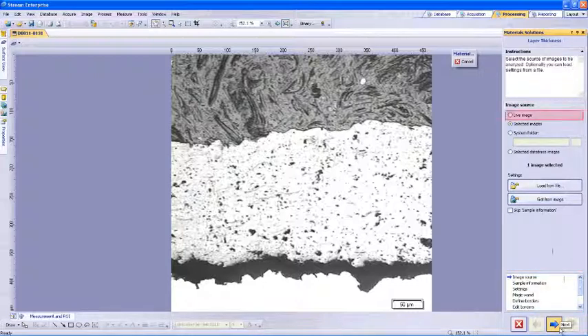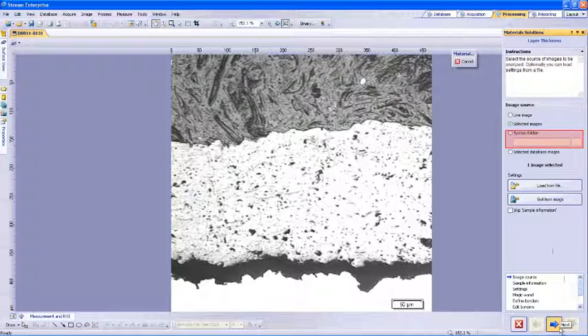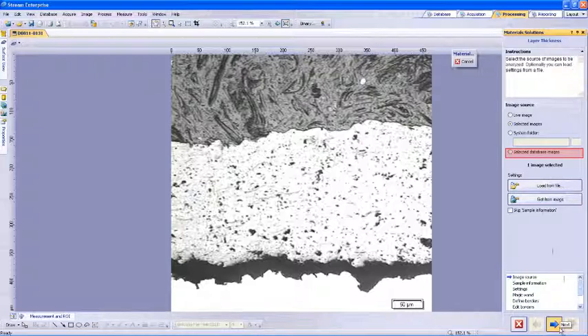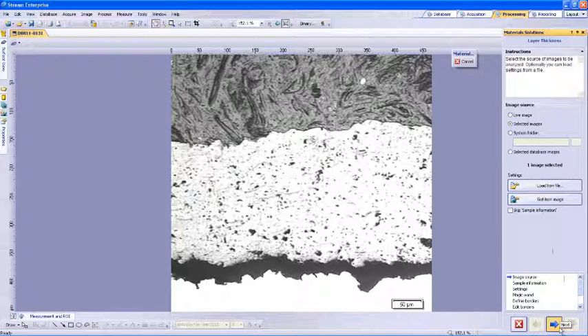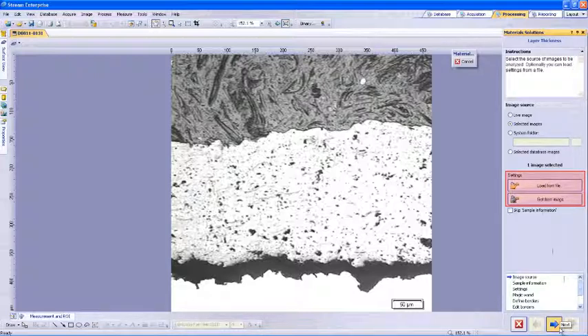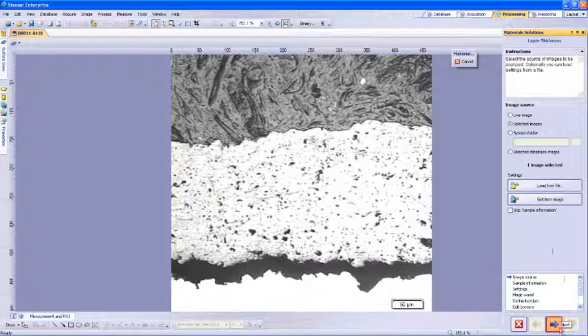The image source selection can be from a new live image, the selected image already opened within the software, a batch of images located within a system folder, or a batch of images you select within the optional Olympus Stream database. The ability to process multiple images as a batch will increase workflow and productivity, also allowing you to average data over a group of images associated with a single sample. Opening the settings at the start of this process will allow the utilization of standard values to increase repeatability in measurement results and also decrease the process time.